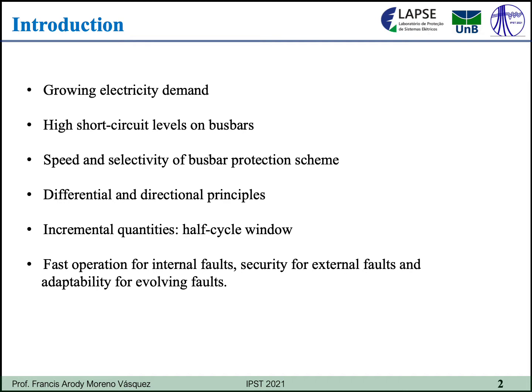And also, these protection schemes are traditionally based on the differential and directional principles, and this work uses these principles simultaneously, and we apply them to incremental quantities which are calculated with a half-cycle window. These incremental quantities are referred to the currents. In any case, any protection scheme must provide fast operation for internal faults, security for external faults, and adaptability for evolving faults.